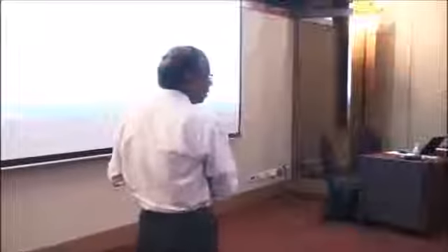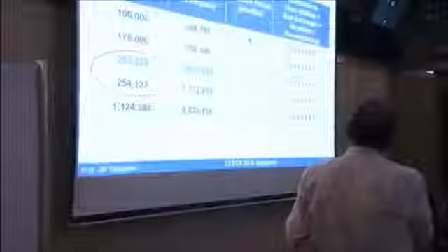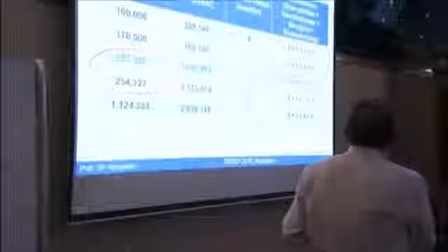I want to emphasize one point. If you look at these two solutions, the cost of retrofit is similar and the utility cost is similar, but the changes to be made are slightly different. You see here, for repiping, you don't have to do 8, you can do only 7, but the resequencing, you have to do more. Sometimes this set of changes could be easier compared to this one. So the engineer can analyze this and choose one of the good solutions.